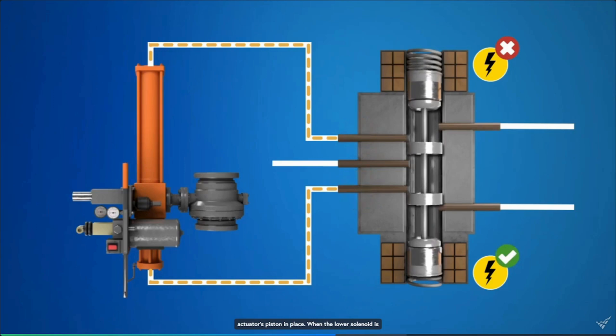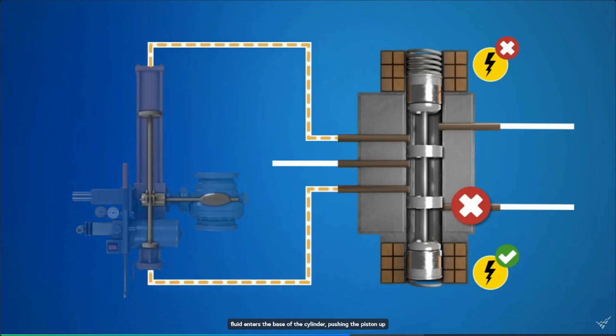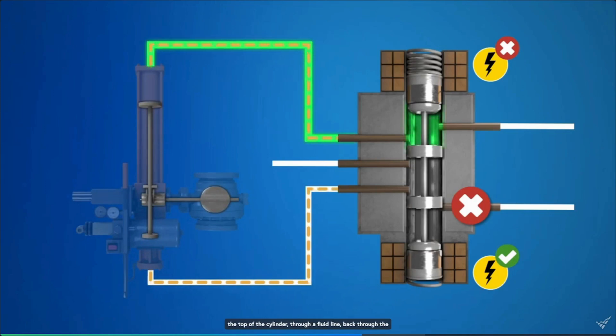When the lower solenoid is energized, the spool is pulled down and hydraulic fluid is supplied through the lower fluid line to the actuator. The fluid enters the base of the cylinder, pushing the piston up and opening the valve. At the same time, fluid is forced out of the top of the cylinder, through a fluid line, back through the pilot valve, out the upper vent port, and back to the hydraulic fluid supply reservoir.